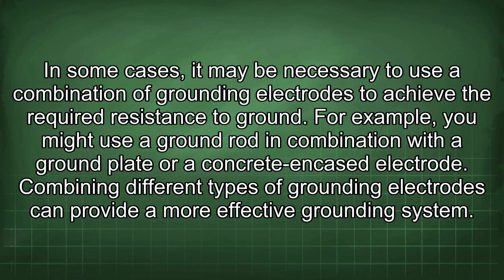In some cases, it may be necessary to use a combination of grounding electrodes to achieve the required resistance to ground. For example, you might use a ground rod in combination with a ground plate or a concrete-encased electrode. Combining different types of grounding electrodes can provide a more effective grounding system.